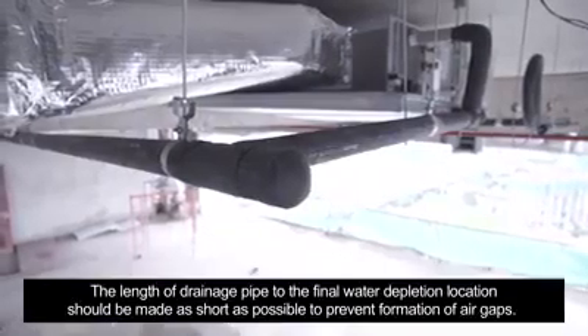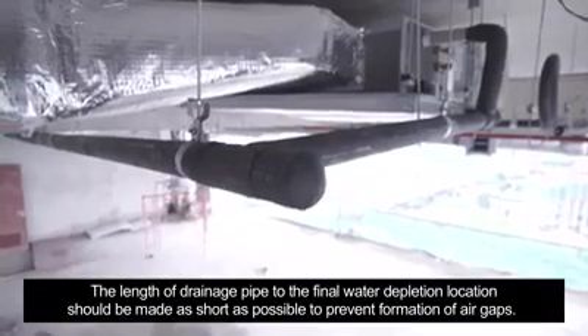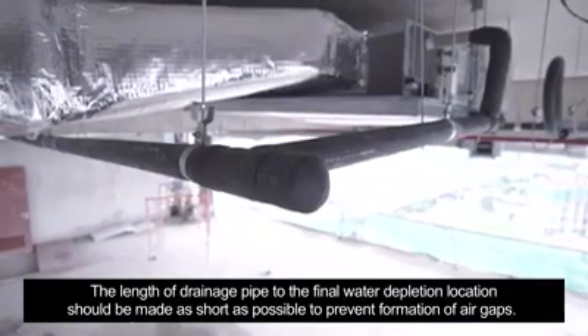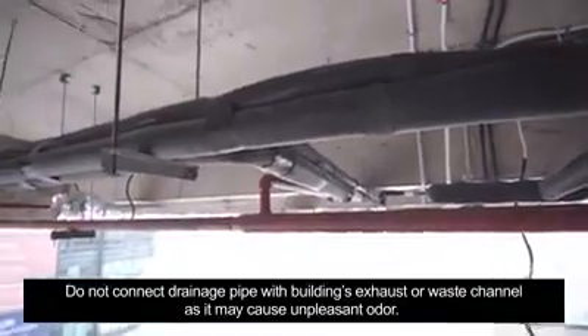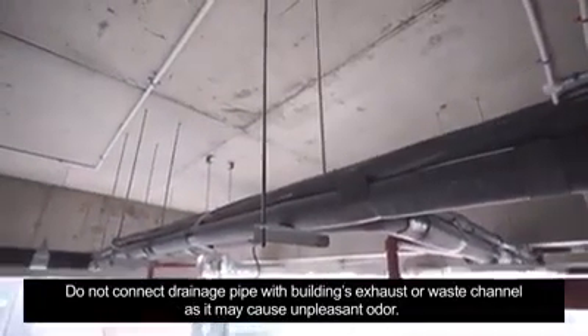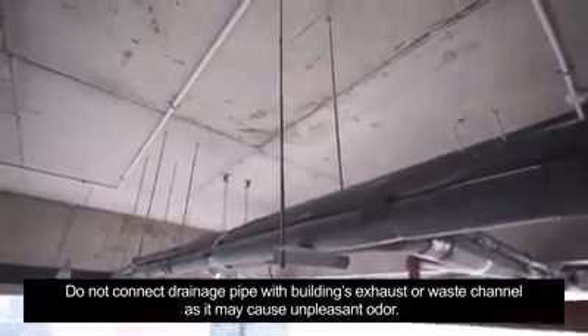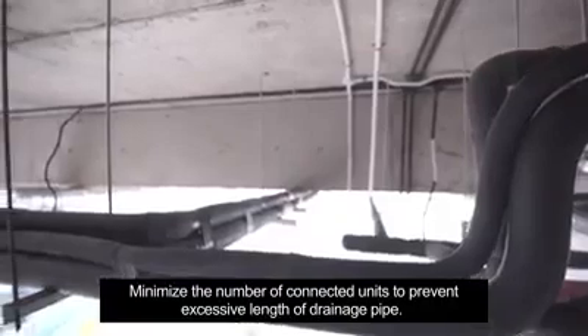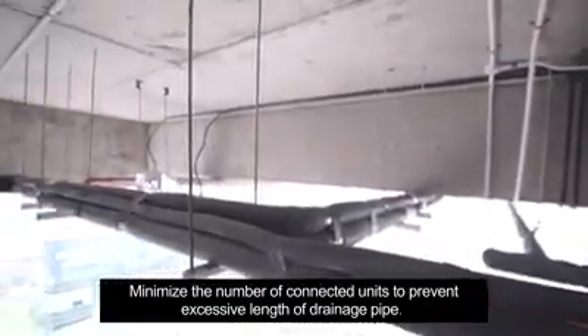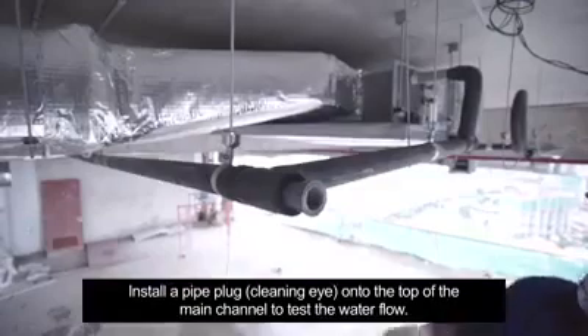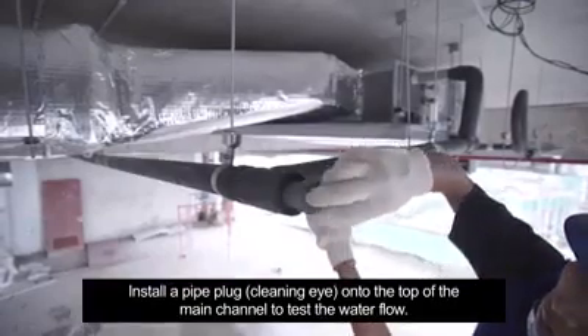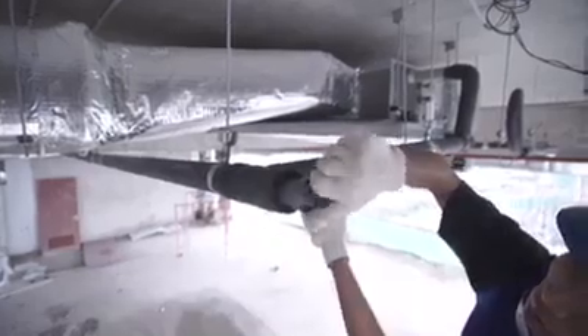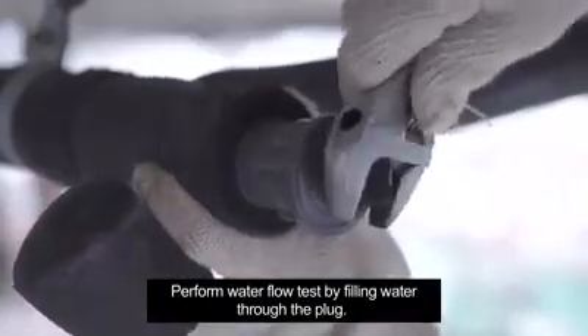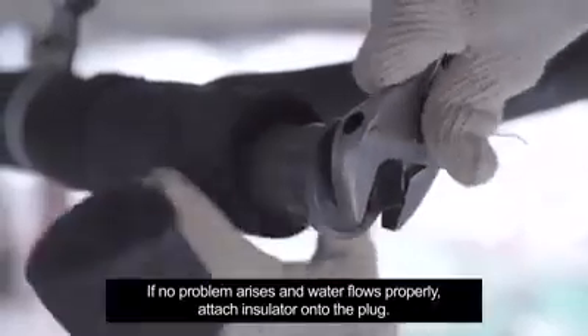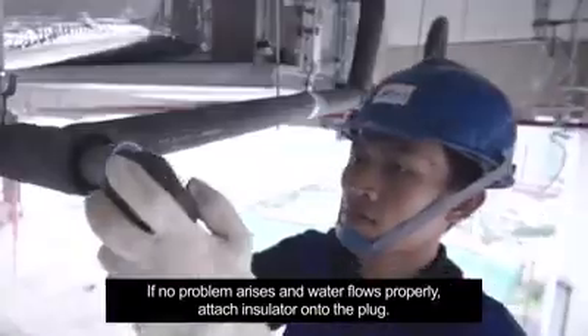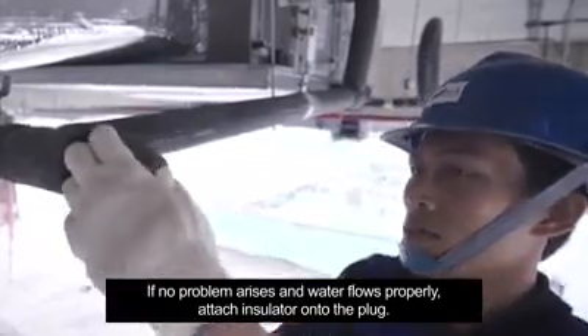The length of drainage pipe to the final water depletion location should be made as short as possible to prevent formation of air gaps. Do not connect drainage pipe with building's exhaust or waste channel as it may cause unpleasant odor. Minimize the number of connected units to prevent excessive length of drainage pipe. Install a pipe plug onto the top of the main channel to test the water flow. Perform water flow test by filling water through the plug. If no problem arises and water flows properly, attach insulator onto the plug.